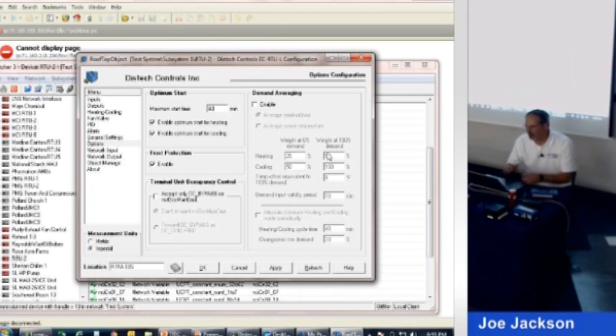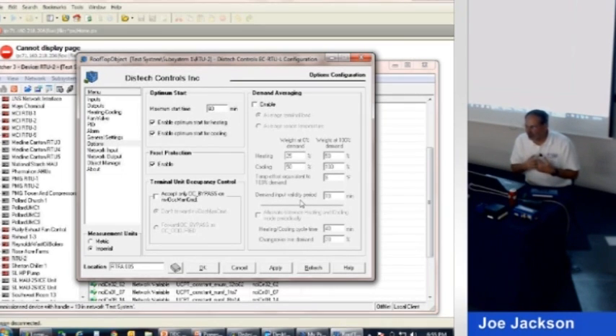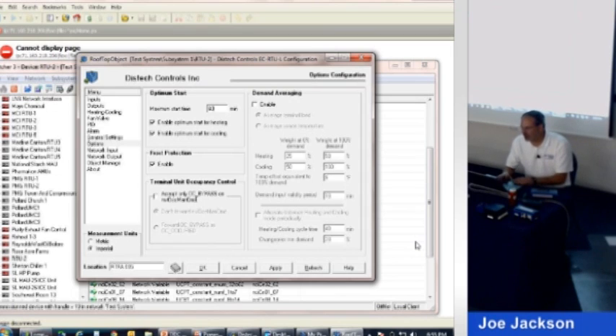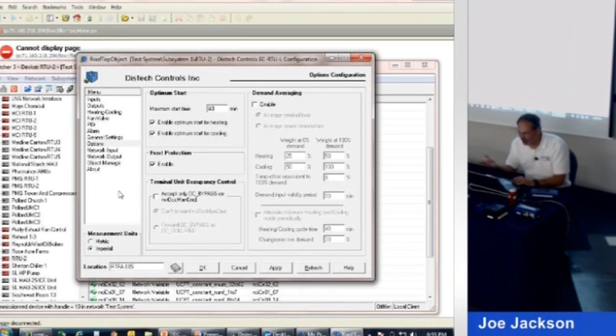We're not going to spend much time here, but those same VAV boxes can give their demand request to the rooftop unit so it knows how to stage on the compressors. And if some of them are calling for heating and some of them are calling for cooling, it's all preset, but basically the way they set it, cooling wins over heating every time. And if you need something special, you can tweak these numbers, or you can actually do a little program inside your Tridium panel to compensate for that. But generally it just works pretty well right out of the box. That's also based on what the VAV boxes are doing. If you're doing it with VAV, we're not.